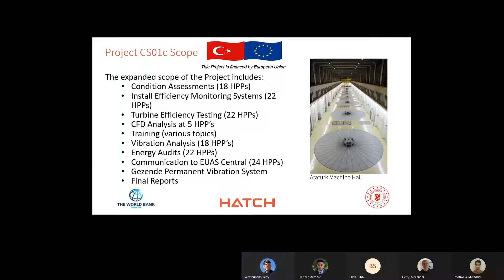Communication systems were installed to send that data from the efficiency monitoring systems back to EUAS Central headquarters. And at one of the stations, Gezende, permanent vibration monitoring systems were installed on those units based on some of the issues they had with vibration at this station. And then finally, the final reports were prepared in order to document all the findings and to present the recommended alternative rehabilitation plans.